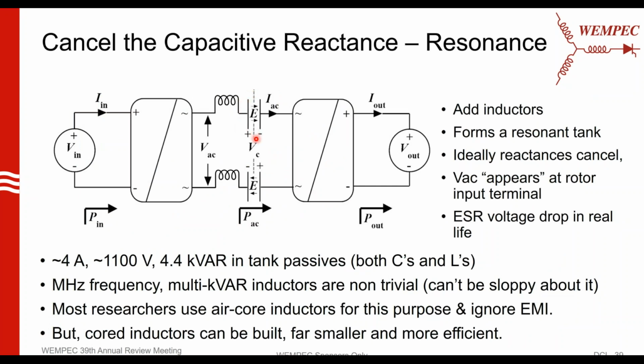These capacitors, even at megahertz frequencies, still have a large amount of reactive impedance, and we need to cancel that out. If I want to push 4 amps through here for my 4 amp field winding, unless I have tremendous amounts of voltage somewhere, which I don't, I have a few hundred volts from a DC bus, then I need to use resonance to cancel out this reactive impedance of the capacitor. So I add inductors in series. In this case, at 4 amps, it's going to be around 4.4 kVARs of reactive impedance that I need to cancel in the capacitor with an inductor.